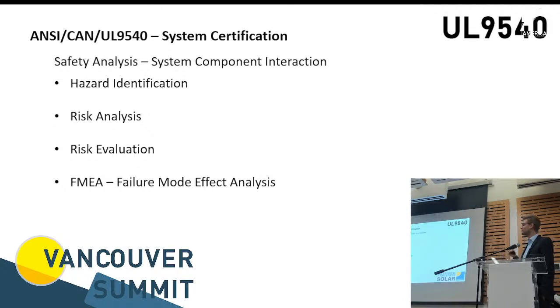So how can a certification identify probable issues that can arise from the combination of a certain battery chemistry, a certain battery module, the size of the system, and the certification body, that can be pretty much any lab, UL, TUV, CSA, Intertek, and whoever it is. They can then identify what kind of hazard that system will present to the home or the application, a risk analysis, a risk evaluation, and very important, a failure mode analysis. So they think about, okay, what can go wrong with that system and what could be the outcome of that fault to a house fire, for example, or the risk to people.